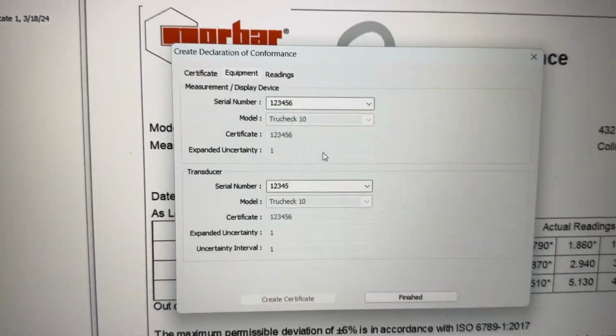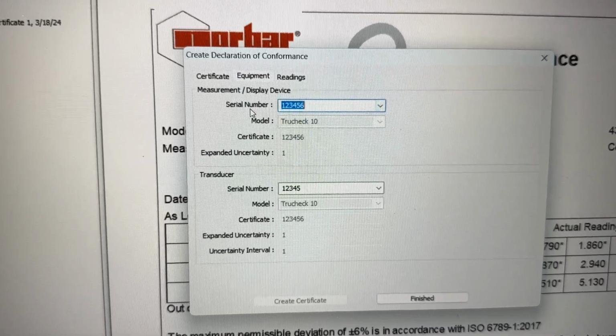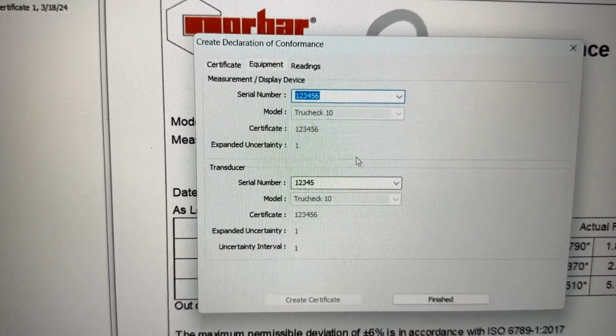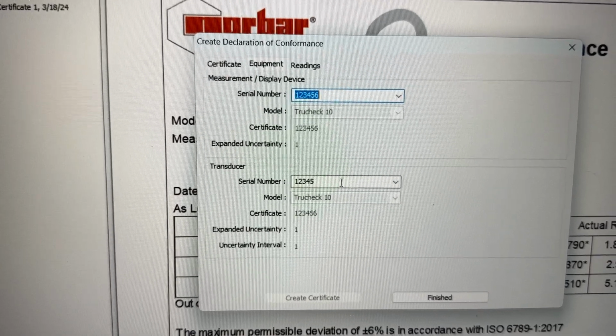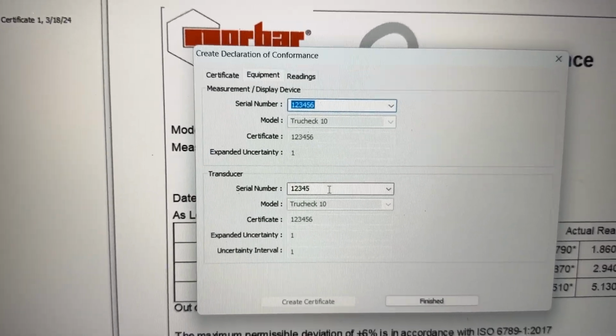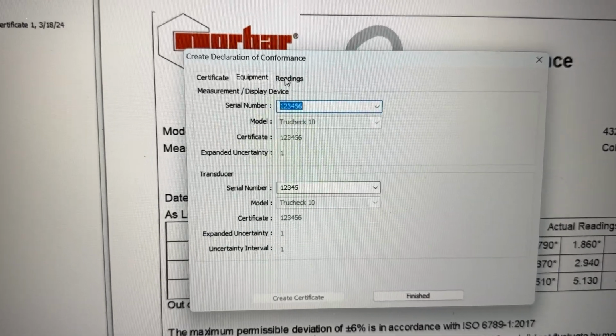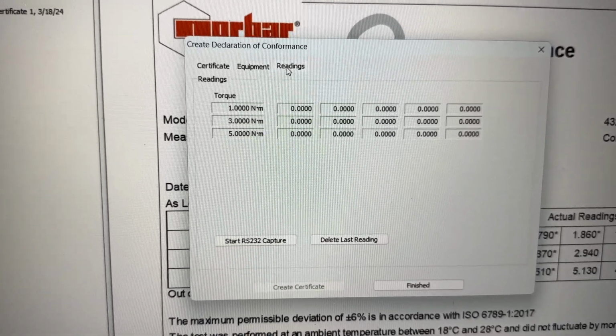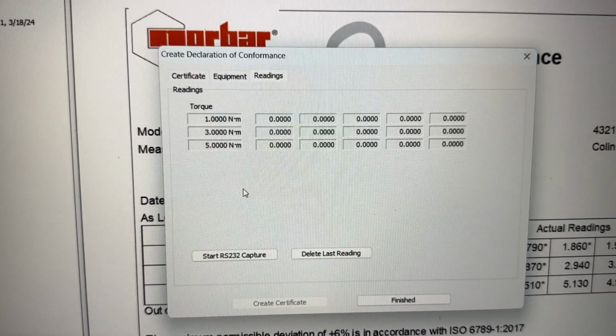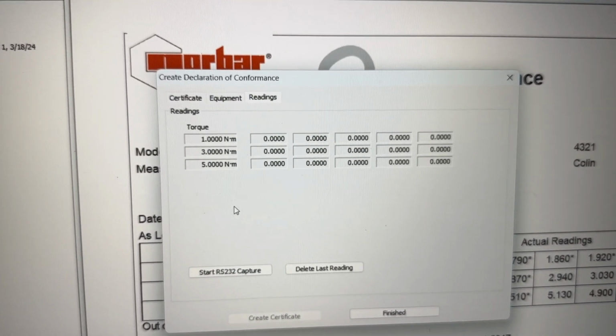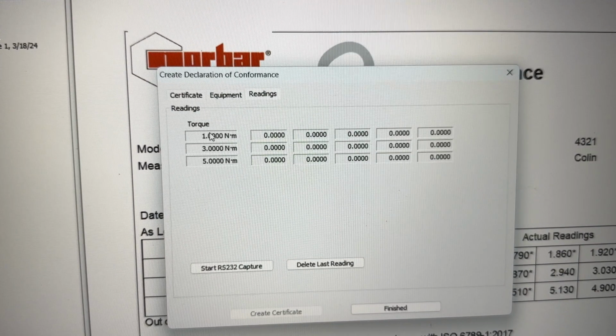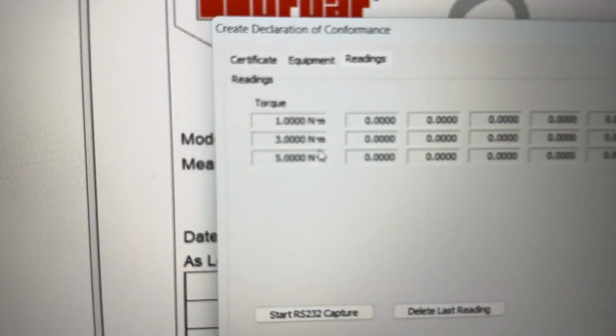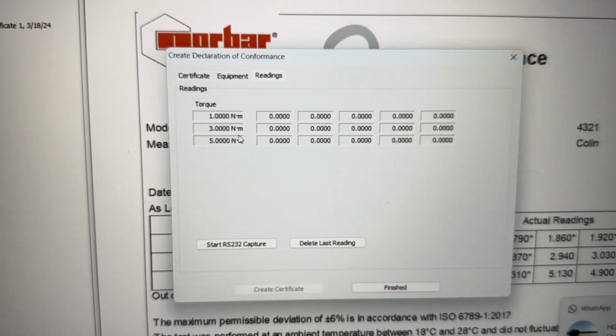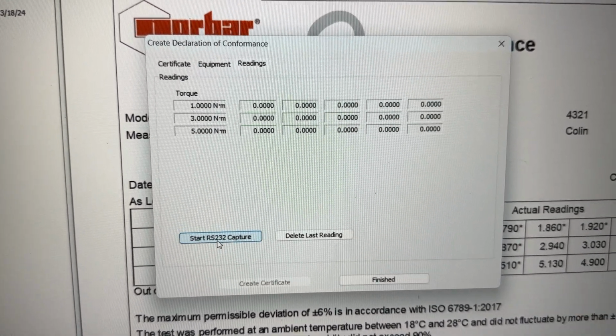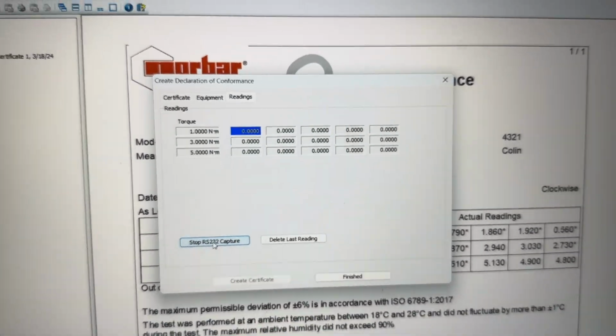The equipment that I'm using is my made up serial number, and then it's a Trucheck 10, which I have here. And it asks for transducer, so we always put it in twice. It's a little bit of a glitch in this software. You have to put it in twice, but once it's in there, it's in there. Now it's showing me the readings it wants me to take. You can change these defaults in the system, but by default it wants to do 20, 60, and 100%. So 1, 3, and 5. And then we can actually start capture by RS-232, and you'll see the blocks go blue waiting for me to do some readings.